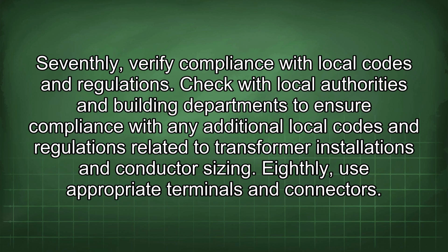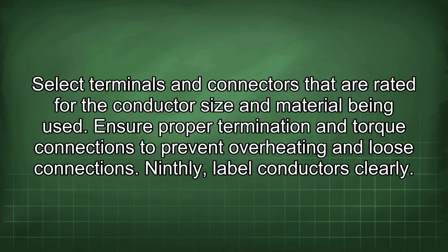Seventhly, verify compliance with local codes and regulations. Check with local authorities and building departments to ensure compliance with any additional local codes and regulations related to transformer installations and conductor sizing. Eighthly, use appropriate terminals and connectors. Select terminals and connectors that are rated for the conductor size and material being used. Ensure proper termination and torque connections to prevent overheating and loose connections.